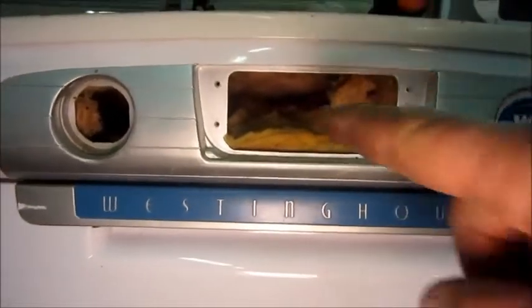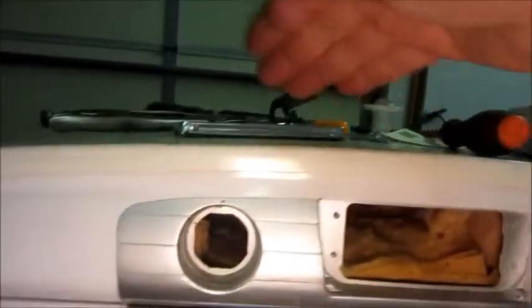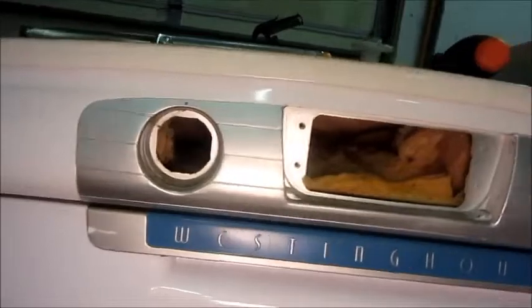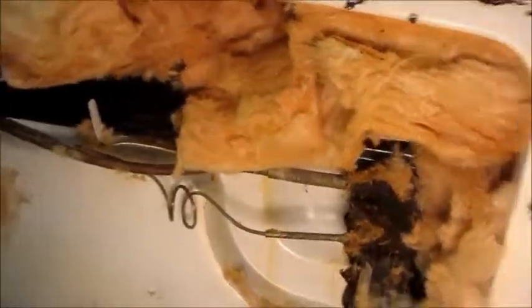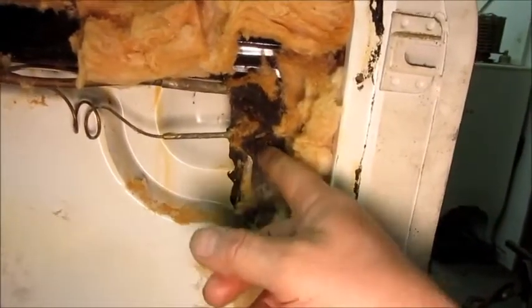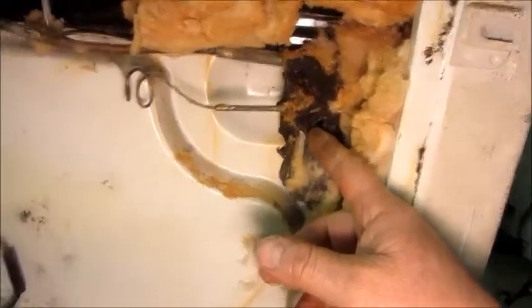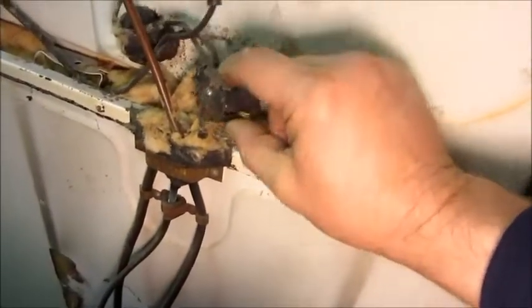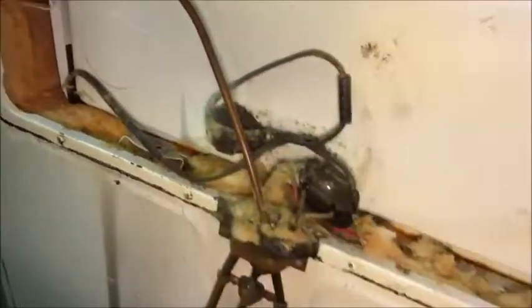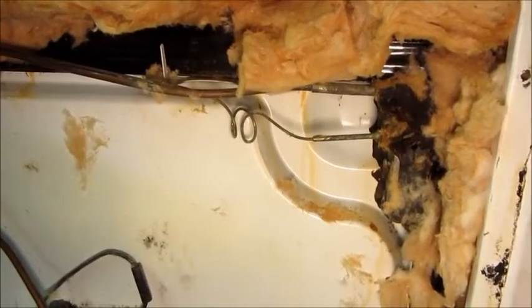So thermostat will go back in through there, push it in, move to the side, and pull it up where the knob fits right through there. And then in the back, the sensing line and cable from the thermostat go through the insulation. Sensing line goes through that rubber bushing to attach the evaporator, and then all the cables were junctioned right here. That's the back of the cabinet light and the cabinet light switch. So all the junctions were available right behind this black cover on the back. So yeah, a lot of this one's definitely got a lot going for it from a design standpoint.